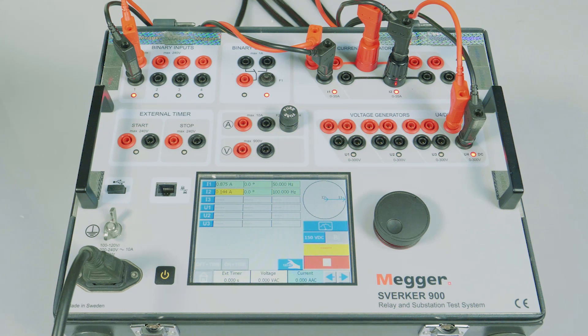we can observe that the CT2 current has gradually increased and the relay dropped out when the CT2 current was 0.144A. The CT1 current is fixed at 0.875A.